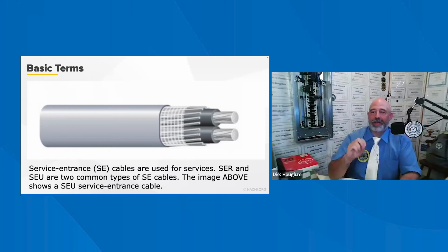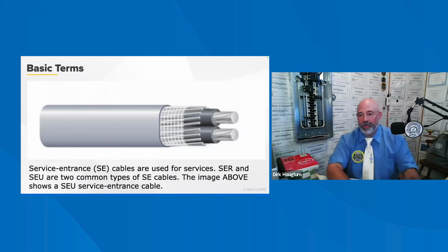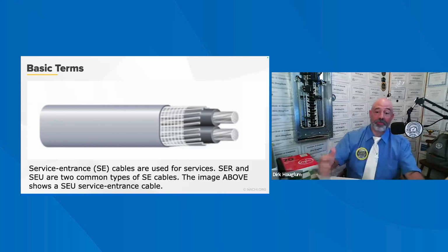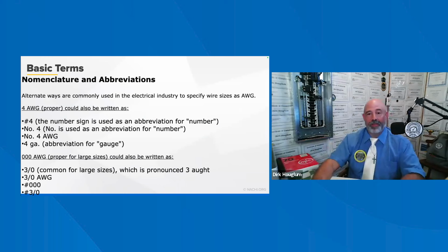It has binder tape to reinforce its shape. It is a round service entrance four-wire cable that typically has up to four conductors and a bare neutral. The cable is designed to be used in a feeder panel and branch circuit. SE or SER cables are equipped with a neutral and a grounding conductor, which makes them perfect for use after the service conductor. I know that was a mouthful.